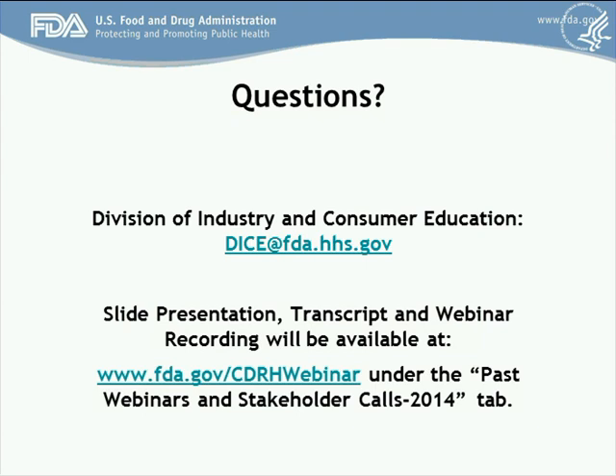And then the other question is, under the guidance, there's a section that goes into different means to limit access to trusted users only. The first bullet says limit access to devices through the authentication of users, for example, user ID and password, smart card, biometric. Would you be able to provide an example where that would be most appropriate? It's difficult to provide an example, it would depend on what your device is and the use environment. There might be use environments where providing such means of authentication would not be practical. For instance, if your device was being used in a surgical suite, that would probably not be an appropriate method of authentication. In other use environments, it might. What the agency would like to see is for you to consider different methods and choose the one most appropriate for your use environment that reduces the risk of unauthorized access.